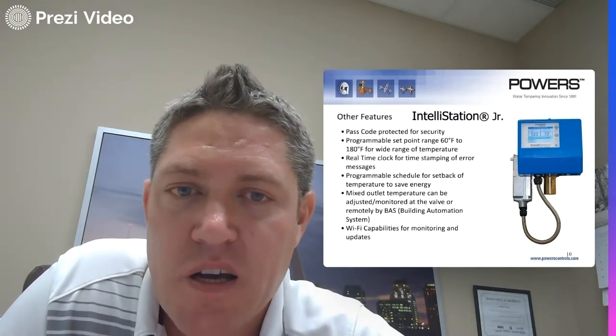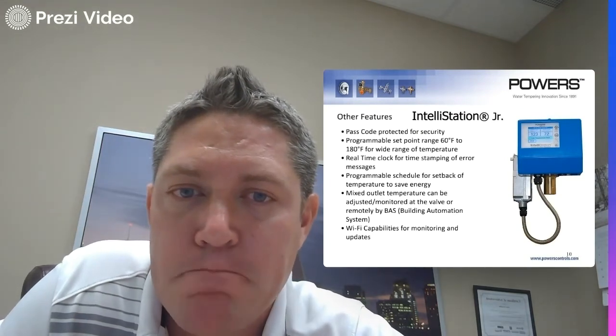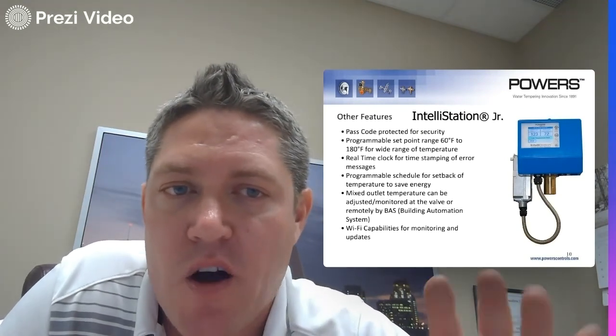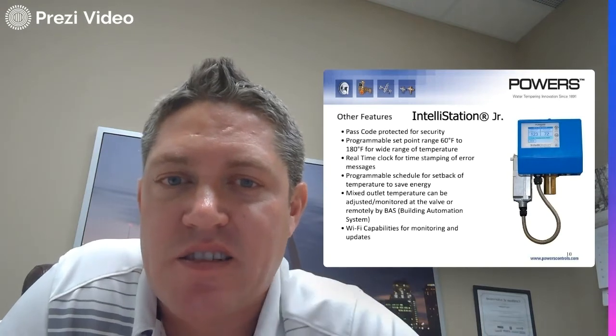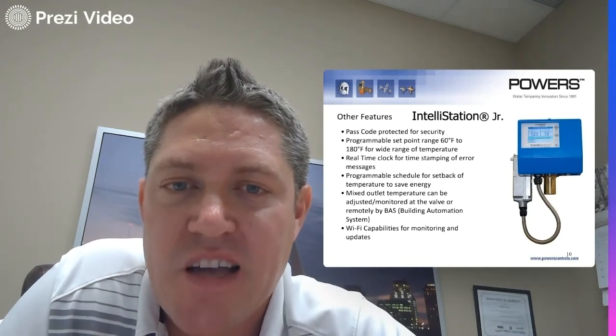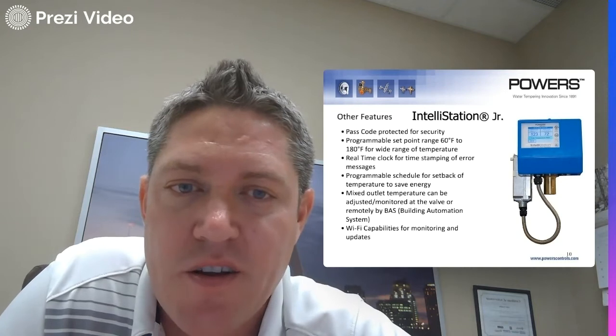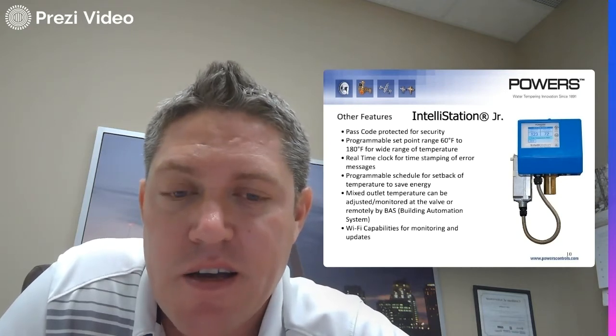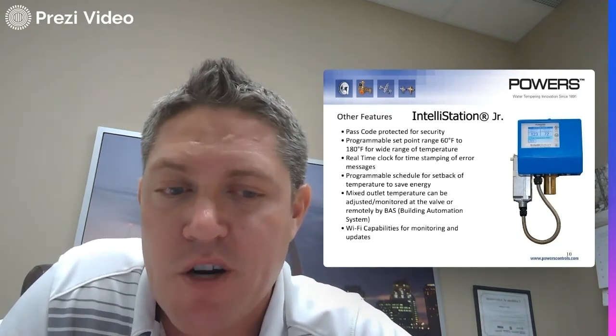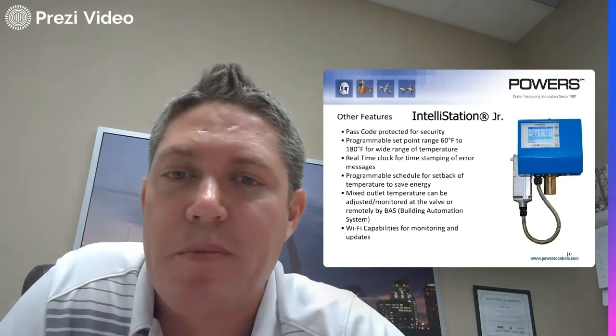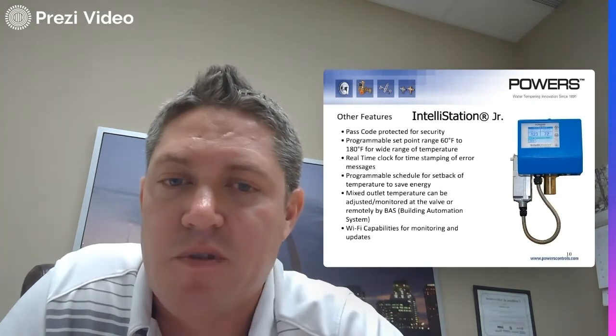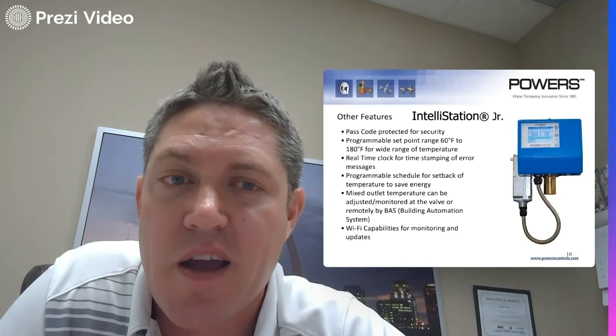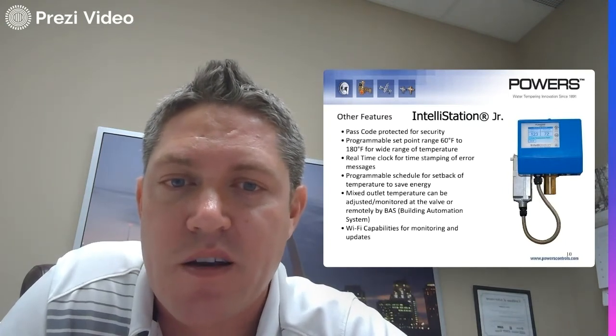Real-time stamping for error messages. Programmable right there on the touch screen, just like the Intellistation Sr. Mixed outlet temperature can be adjusted or monitored at the valve. You don't need to bring out a computer or a module chip like a zip thumb drive like you do on some other brands. It's all right there on the touch screen.